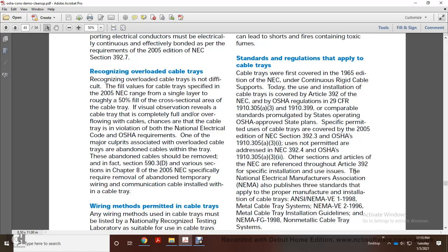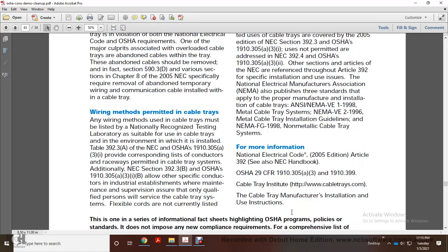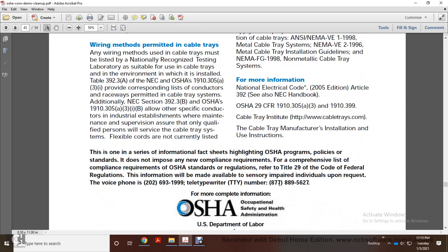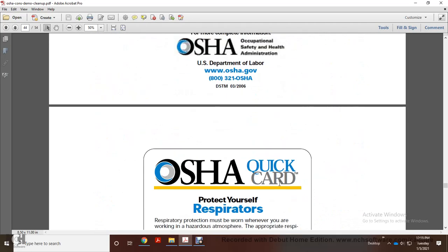Specific installation uses. National Electrical Manufacturers Association standards also apply to the proper manufacture and installation of cable trays. ANSI/NEMA VE 1 1998 covers metal cable trays. NEMA VE 2 1996 covers metal cable tray installation guidelines. NEMA FG 1 1998 covers non-metallic cable tray systems. For more information, see the National Electrical Code, OSHA 29 CFR 1910, the Cable Tray Institute, and cable tray manufacturer installation and use instructions.